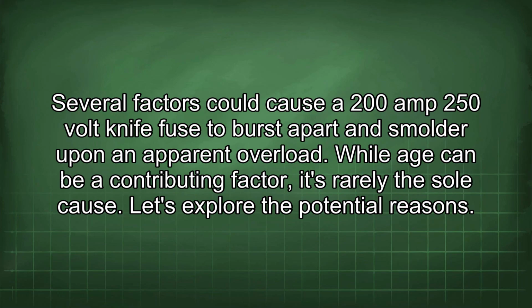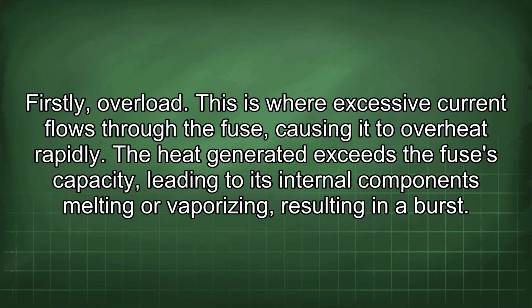Several factors could cause a 200 amp 250-volt knife fuse to burst apart and smolder upon an apparent overload. While age can be a contributing factor, it's rarely the sole cause. Let's explore the potential reasons. Firstly, overload. This is where excessive current flows through the fuse, causing it to overheat rapidly. The heat generated exceeds the fuse's capacity, leading to its internal components melting or vaporizing, resulting in a burst.